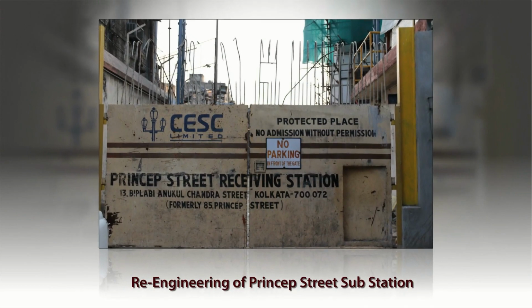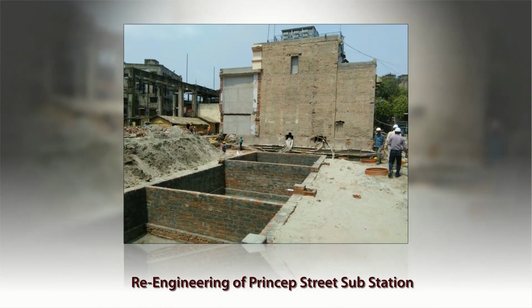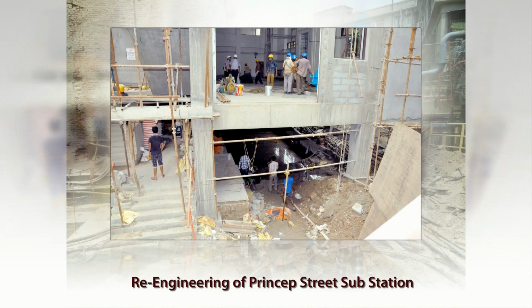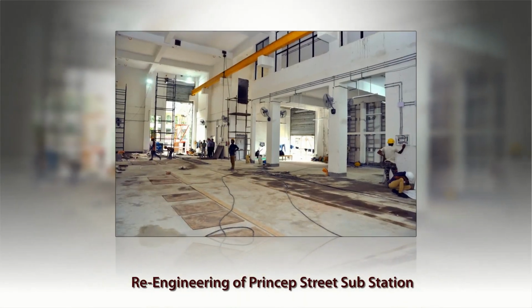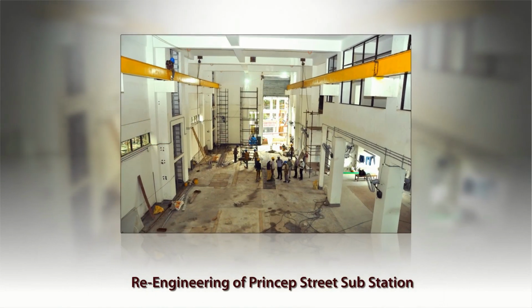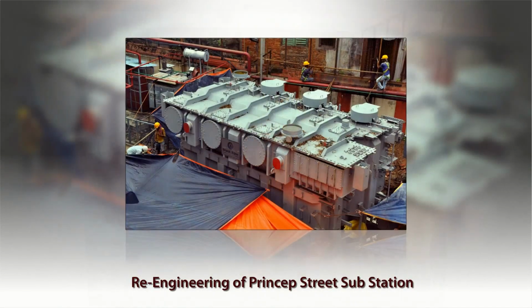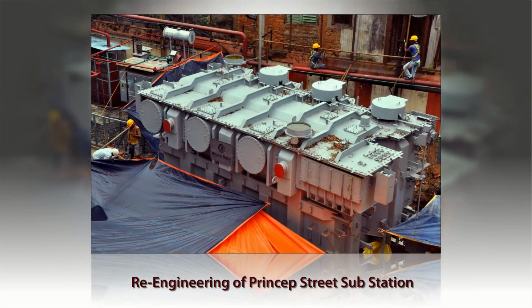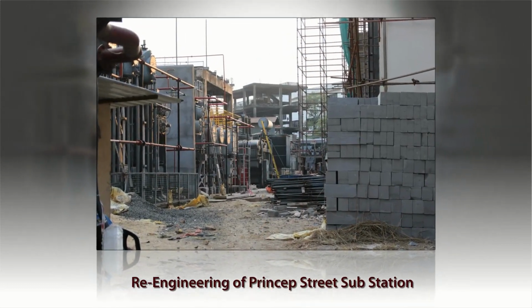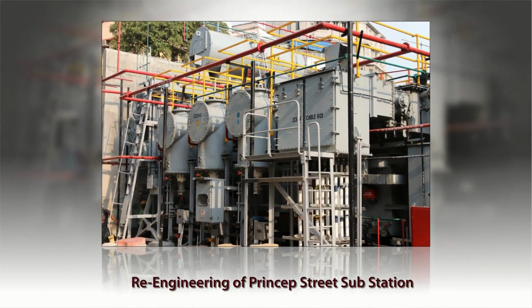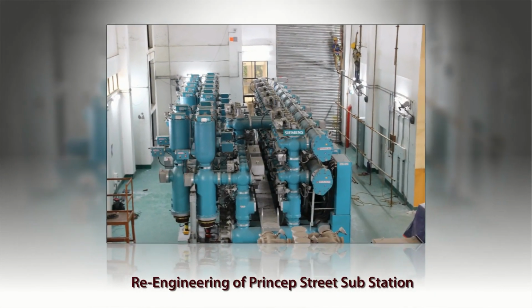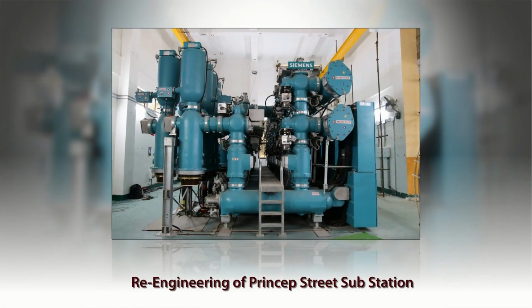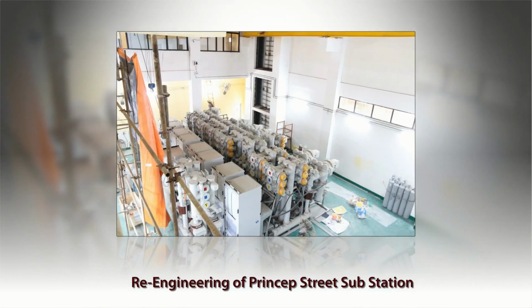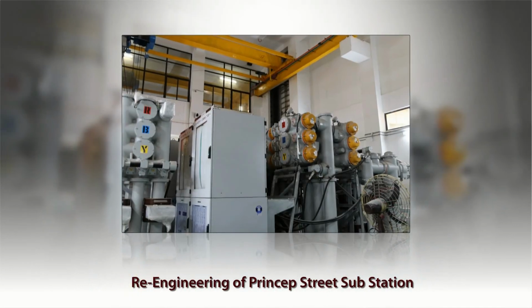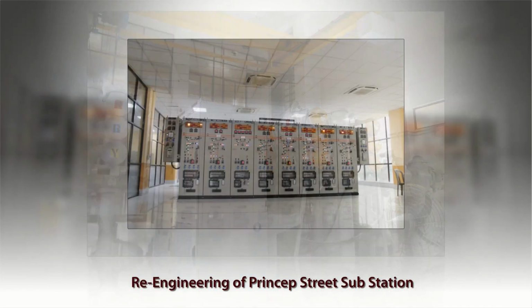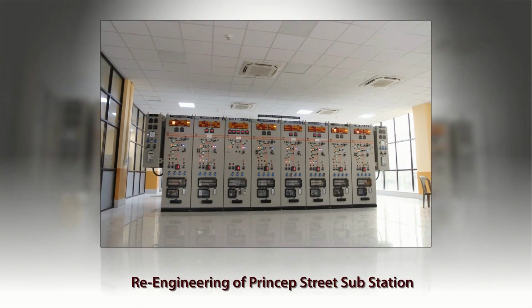Prinsep Street substation is now being re-engineered for capacity augmentation from 250 MVA to 325 MVA and voltage upgradation from 132 kV to 220 kV to draw additional power to meet system growth. The network reorganization is being done, maintaining all existing supply. CESC has implemented many pilot projects with the latest technologies and has plans to install similar equipment in upcoming projects.